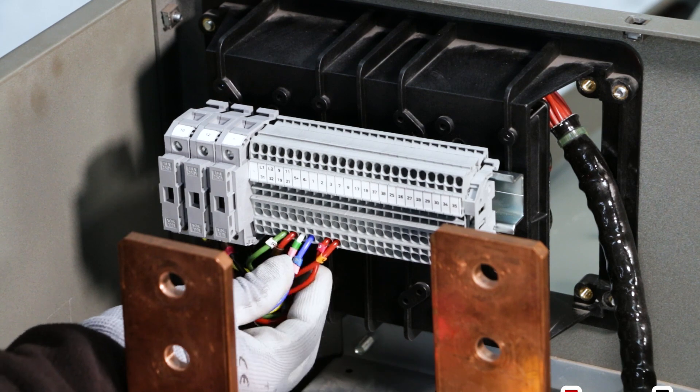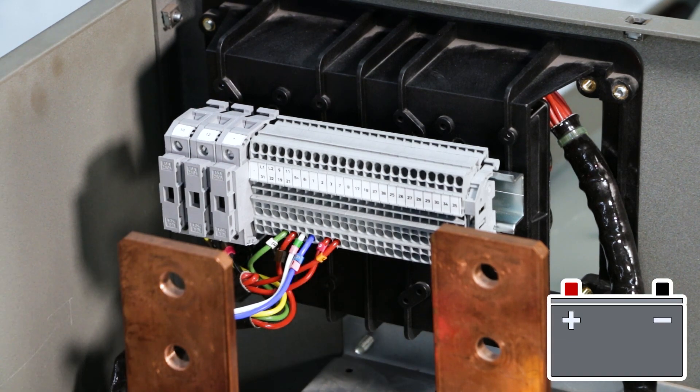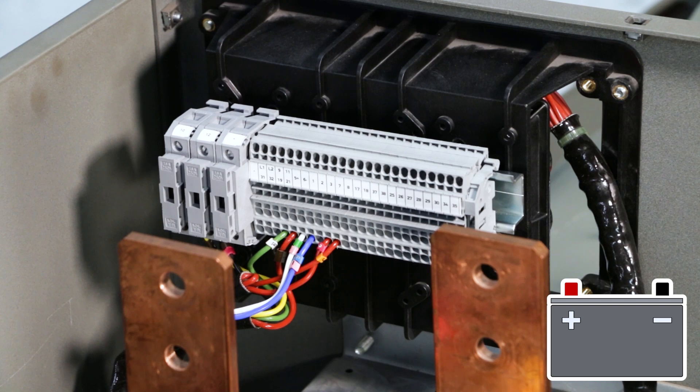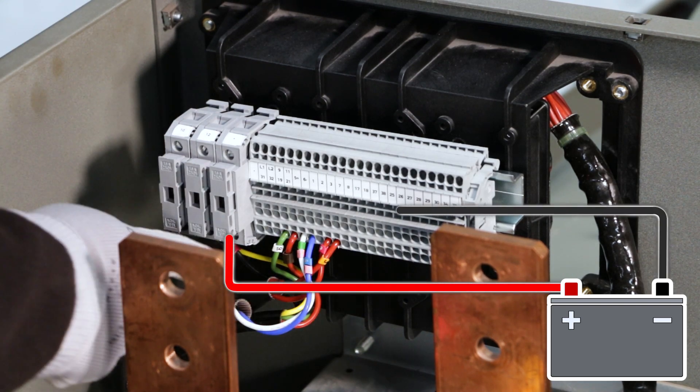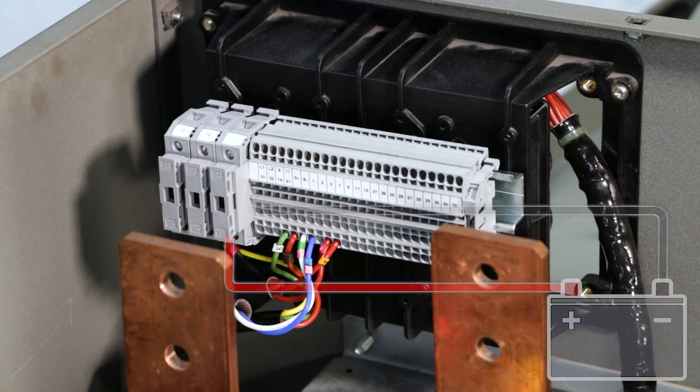To operate, the D550 requires an auxiliary 12-24 volts power supply not included in our supply. This power supply must be installed between the plus and minus terminals of the terminal block on the alternator side.